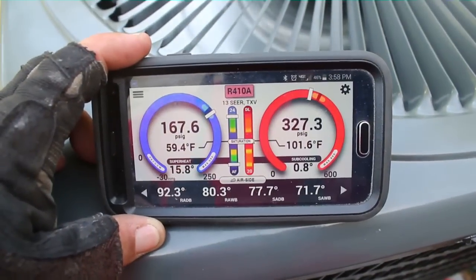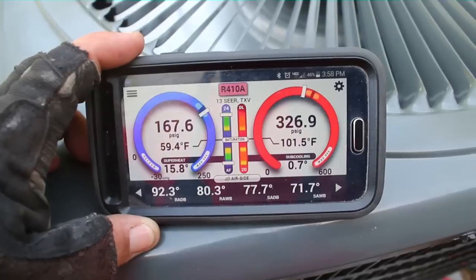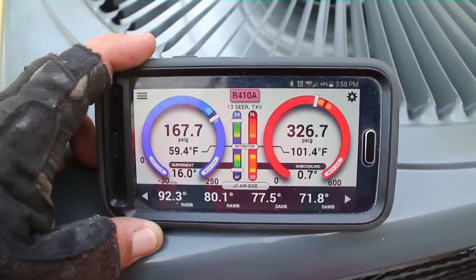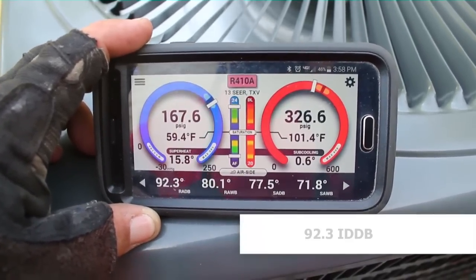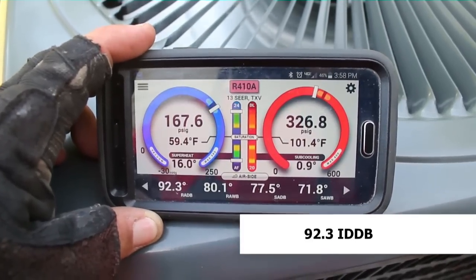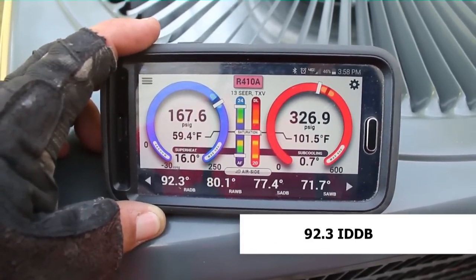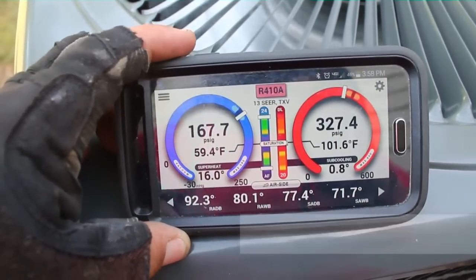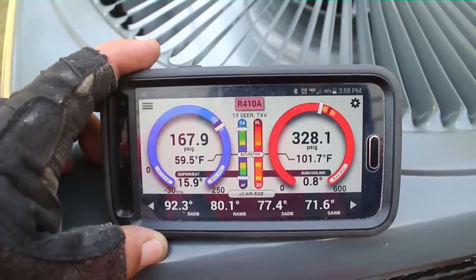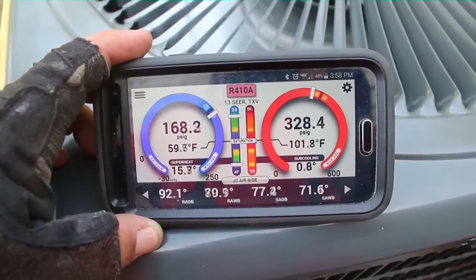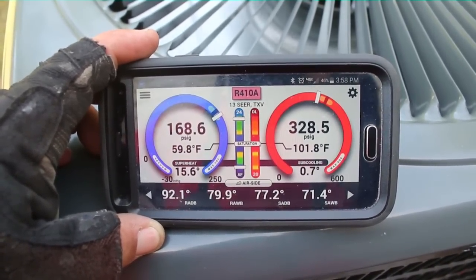We have our system all started up. You see we have a 327 over 167 refrigerant pressure, and you know it's hot inside if it's almost 170 pounds on the suction side. We have a TXV inside. You see we're about on target as far as the suction pressure. TXV is actually regulating that. We don't have much subcooling. We'll have to put in some more refrigerant.